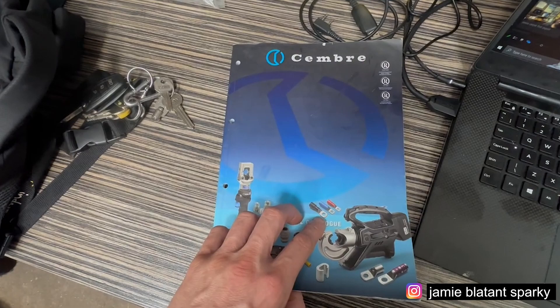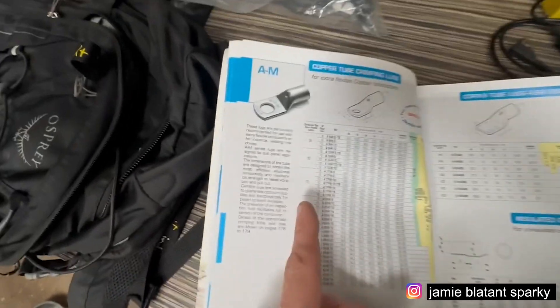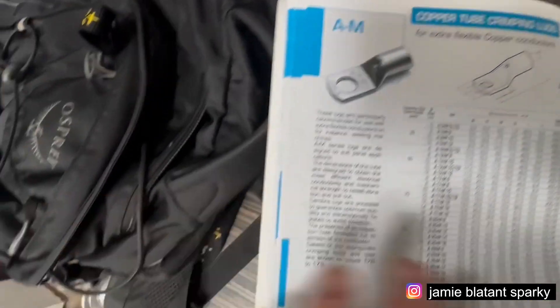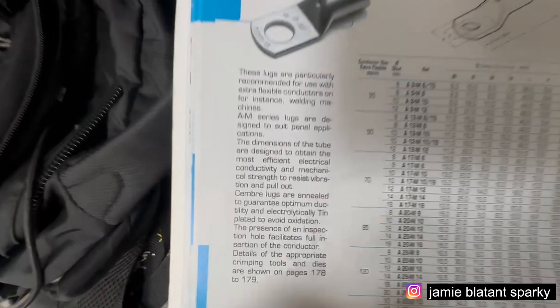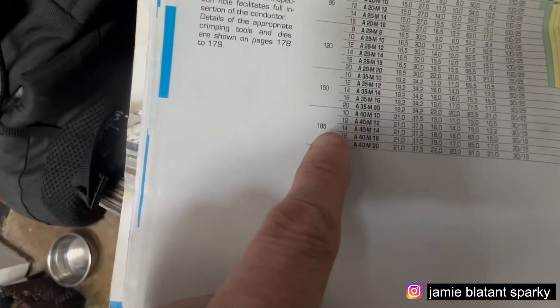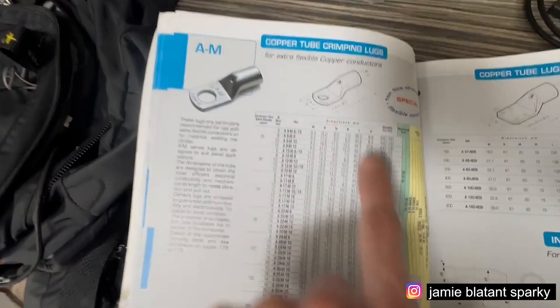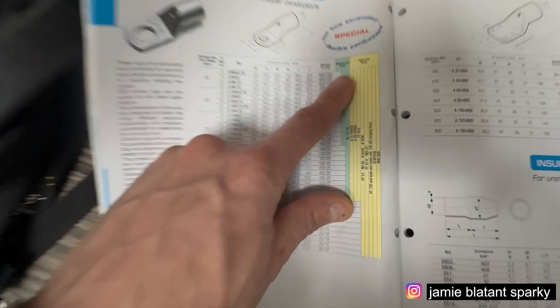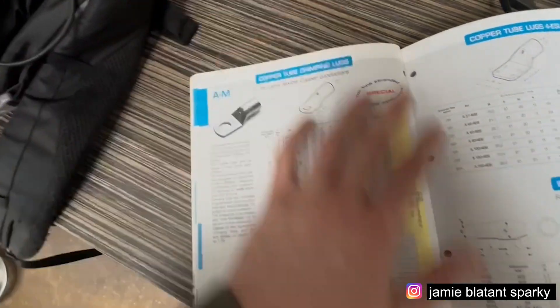Here is the Cembre catalogue. I've got a copy because I bought the stuff off them, but you can get it digitally. For example, you've got the AM lugs - there's the AM lug, which is like a standard lug. There's all sorts of lugs in there, like the A4 ESR which are your transformer lugs. An AM lug's a pretty standard lug. It tells you the size, the stud size. So in 35mm you can get 6, 8, 10, and 12mm stud. In 185mm you can get 10, 12, 14, 16, and 20mm. It tells you all the dimensions and the die reference, and which tools they've got.